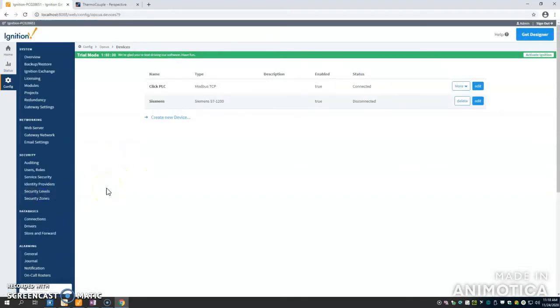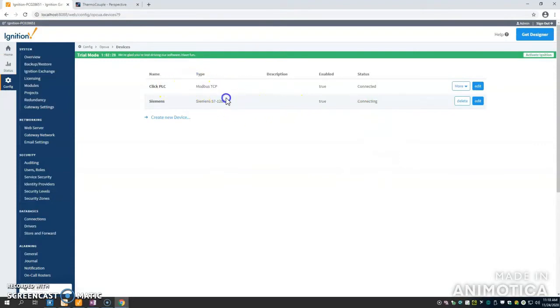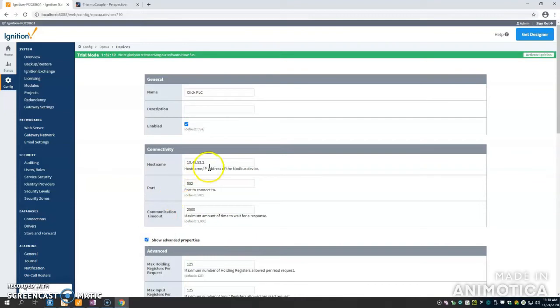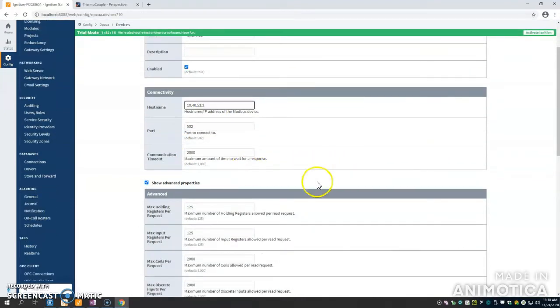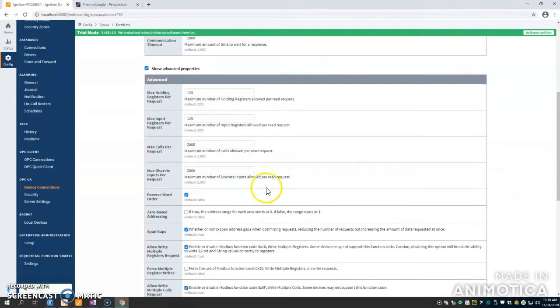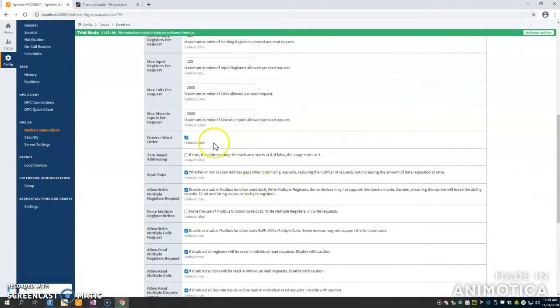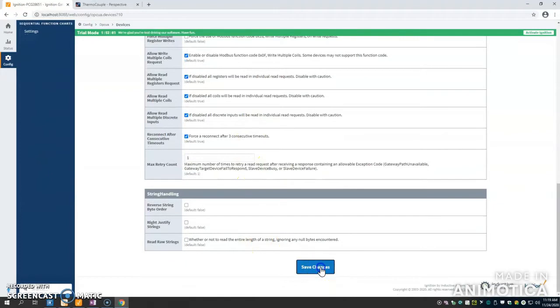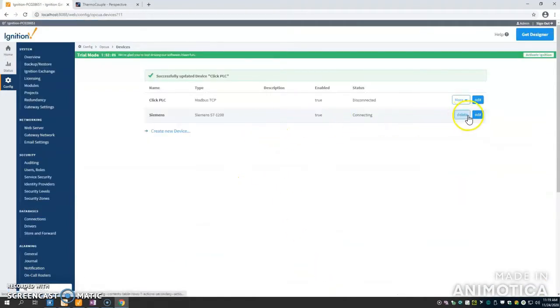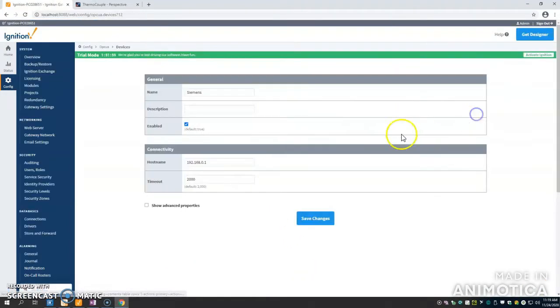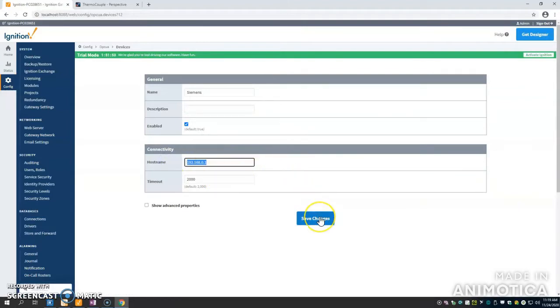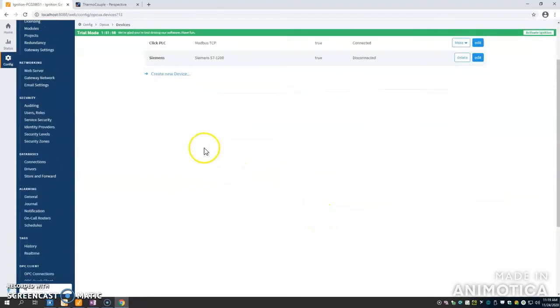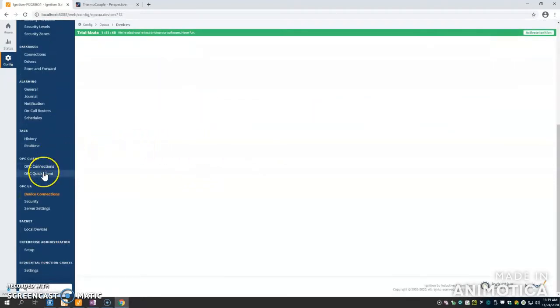I have a Click PLC from Automation Direct hooked up, which is fairly easy, just via IP, same as Siemens. But over here, you can see all you have to do is hook in the IP, fairly easy, go into Click PLC, figure out what it is, plug it in, not too difficult, and then there's a lot of different settings that most of the times aren't necessary. This was important, the reverse word order, though, because the floating points came in backwards. The two bits did not come through correctly, which is a problem. The Siemens one was super easy, though. They support tag browsing, so that was even easier than the Click. It was very quick to set up.